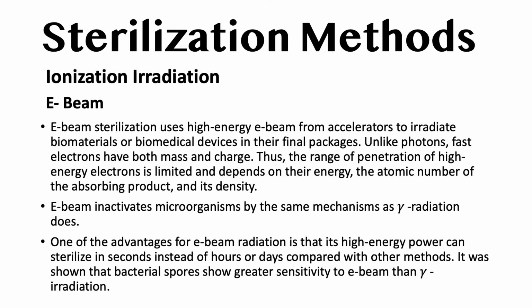Electron beam. Electron beam sterilization uses a high energy electron beam from accelerators to irradiate biomaterials or biomedical devices in their final packages. Unlike photons, fast electrons have both mass and charge. Thus, the range of penetration of high energy electrons is limited and depends on their energy, the atomic number of the absorbing product, and its density. Electron beam inactivates microorganisms by the same mechanism as gamma radiation does.